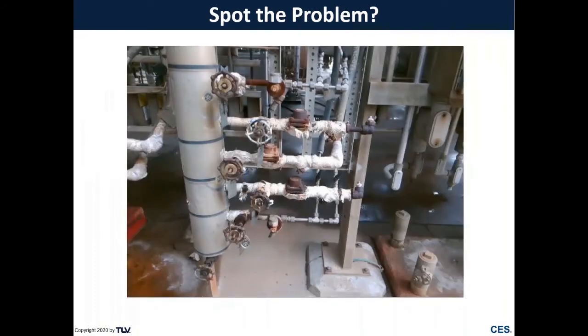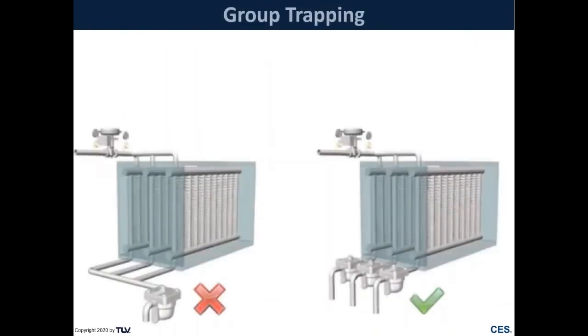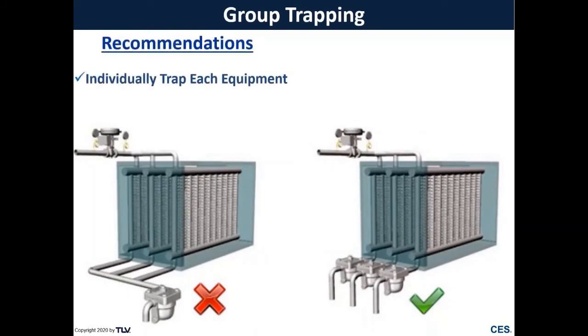Here's another example where multiple tracing lines drain to common steam traps in a manifold. Two tracer circuits go to one steam trap — one circuit can drain while the other backs up condensate due to different loads and pressure drops across the circuits, potentially leading to decreased process temperatures and thermal maintenance issues. The solution to group trapping is simple: individual steam traps on each piece of steam-using equipment. Each section of an air coil needs a separate trap, and each tracer circuit needs its own steam trap to optimize heating.